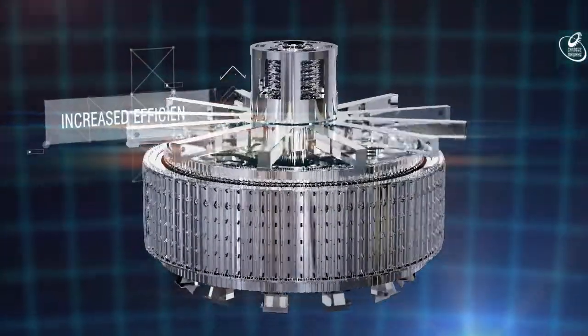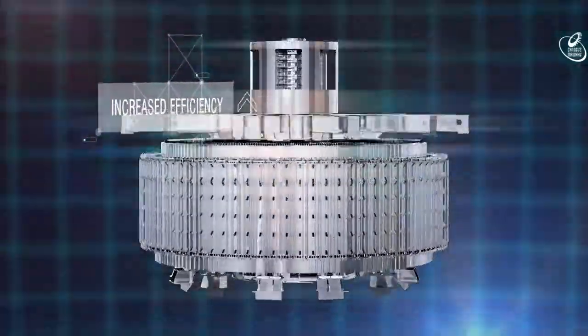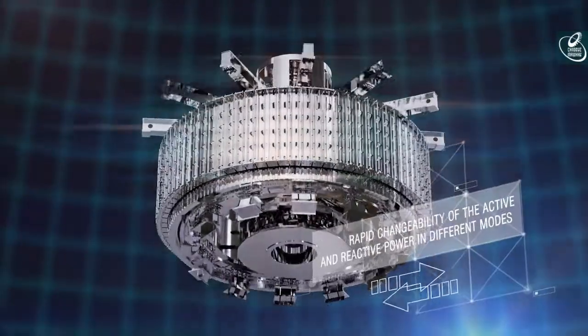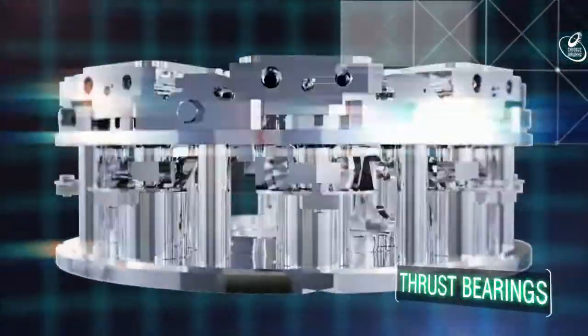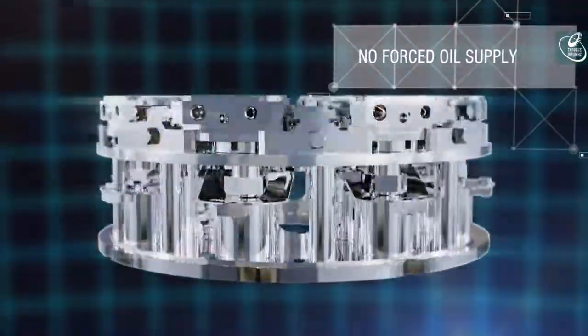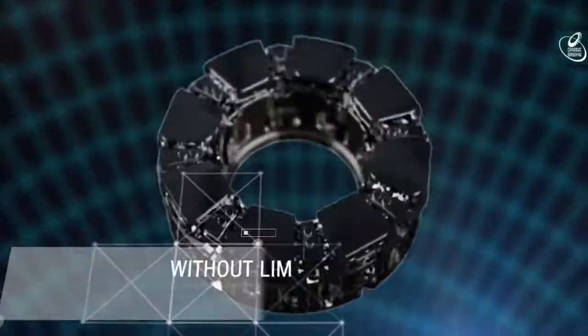The company's innovative solution is an asynchronous motor generator for pumped storage power plants. Key features include increased average efficiency in turbine and pump modes, rapid changeability of active and reactive power, fast frequency control of the power system in generator and motor modes, and high level of dynamic stability in comparison with synchronous generators. All hydro generators manufactured by Power Machines are equipped with reliable thrust bearings.